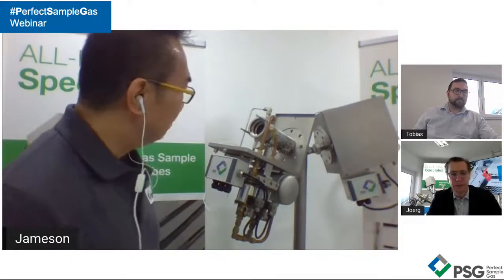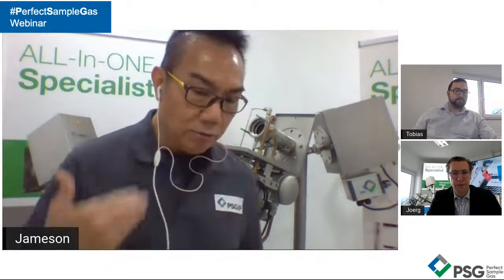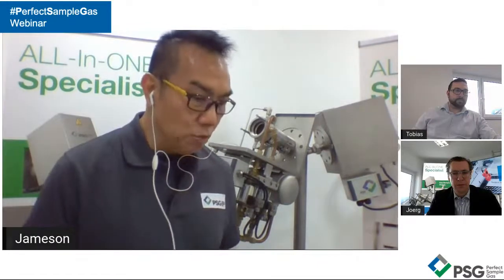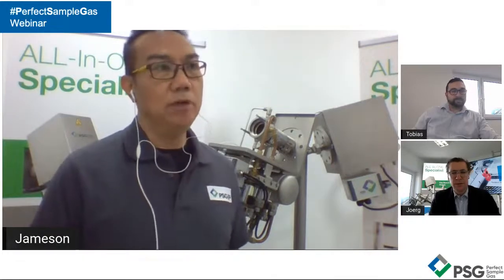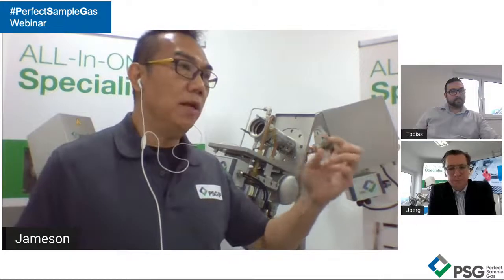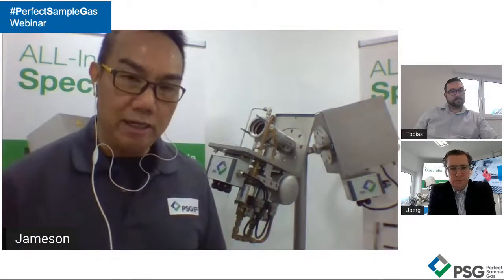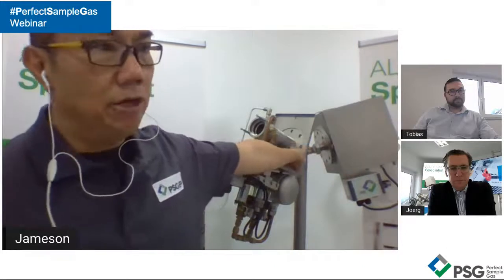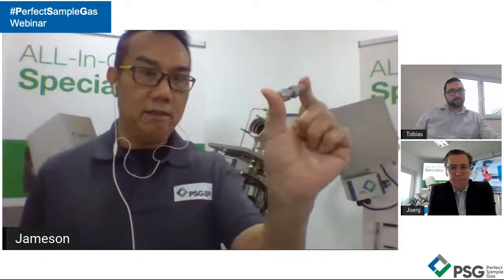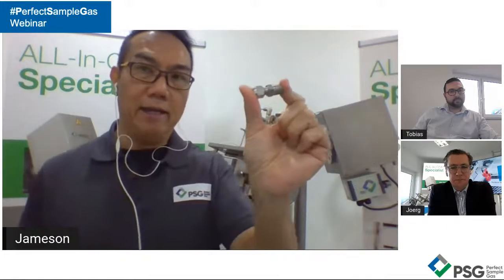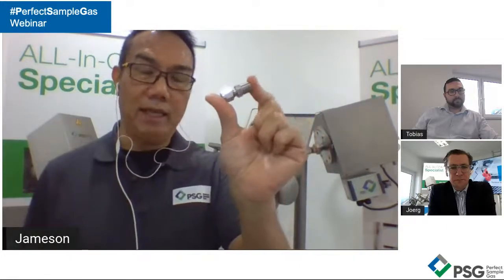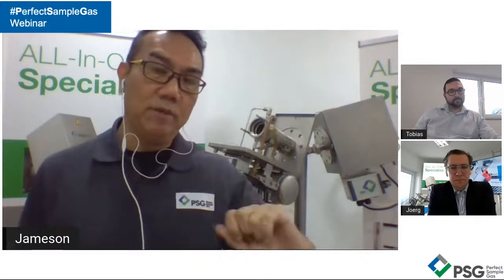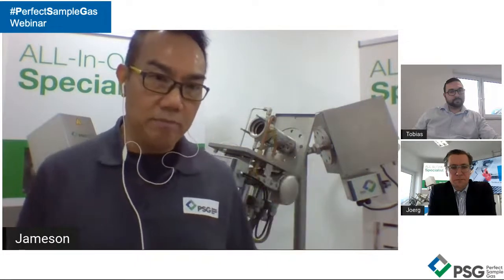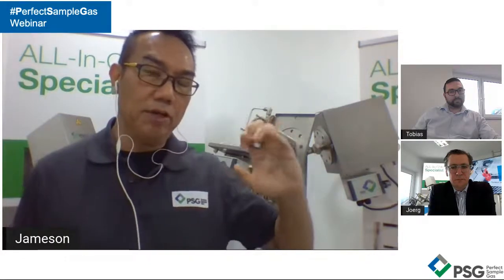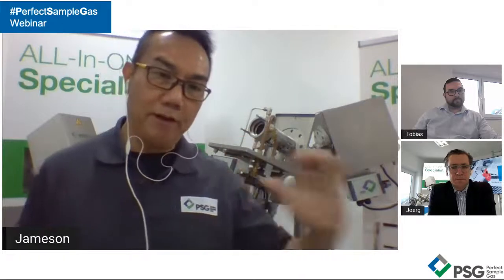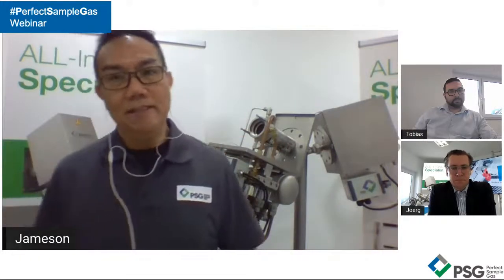Lastly, when we do a back purge, we don't want the sample to be altered, so we don't want the back purge air introduced into the analyzer. What we have is a pressure reduction valve - when pressure is higher than 1.8 bar absolute, this mechanical valve automatically shuts, stopping air from going back to the analyzer. This concentrates the pressurized air forward to the probe and flushes it into the process.